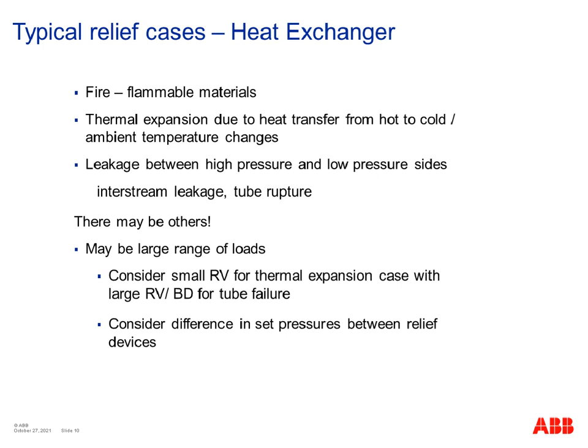For example, you could have the thermal expansion case with a set pressure lower than the point at which the bursting disc or the relief valve would open for tube failure. Then you can avoid disturbing the larger relief device in the event of the smaller relief case happening. So you could allow that thermal expansion relief flow to leave via the relief valve without having your bursting disc opening at that point and then having to deal with recovery from that bursting disc failure. So you consider the differences in set pressures between the relief devices to cater for the different relief events that you've come up with following your structured approach to working out what relief cases you actually have.